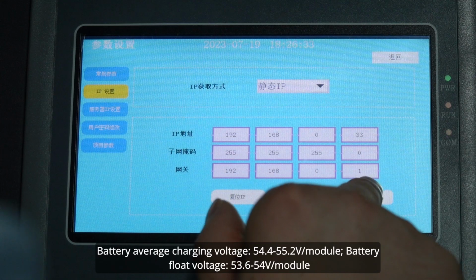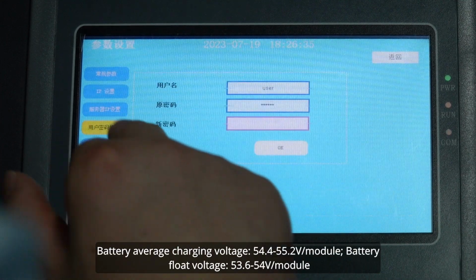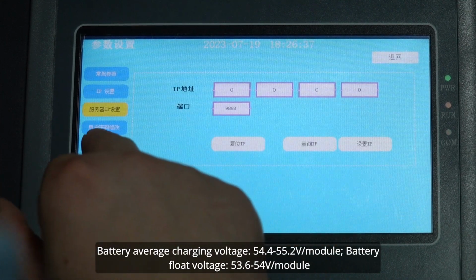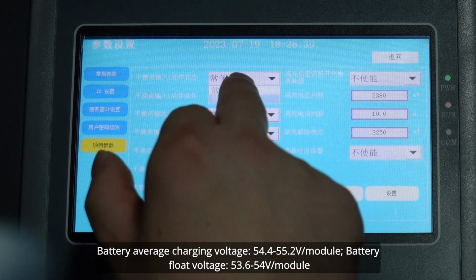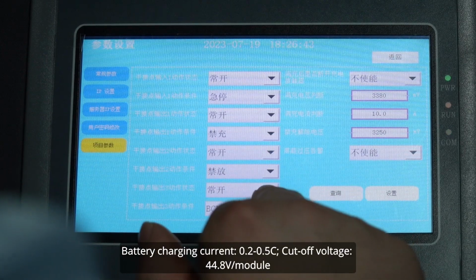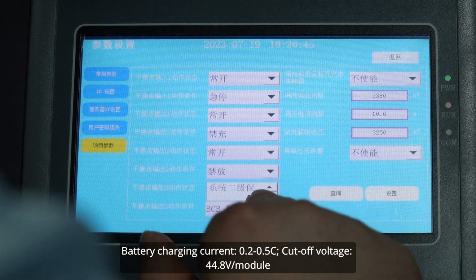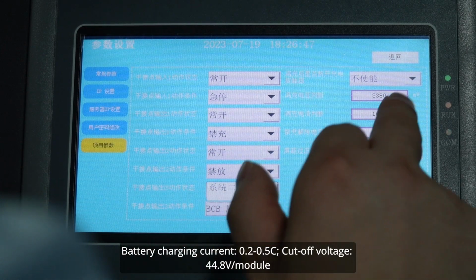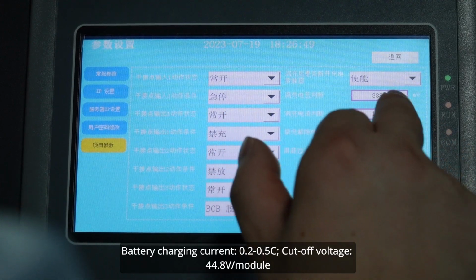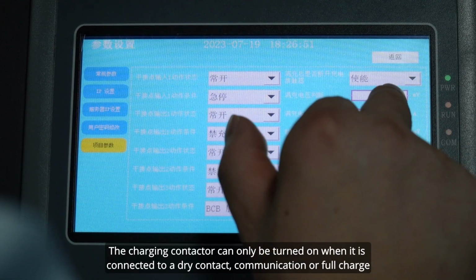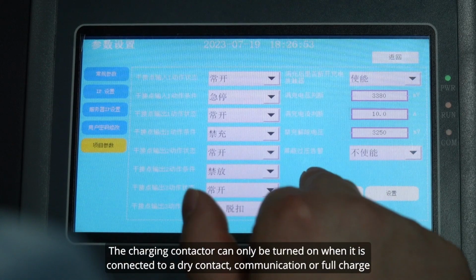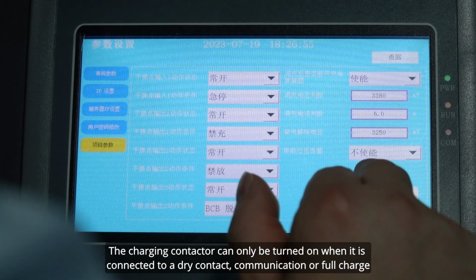Step 6. UPS parameter settings. Battery average charging voltage, 54.4-55.2V/module. Battery float voltage, 53.6-54V/module. Battery charging current, 0.2-0.5C. Cutoff voltage, 44.8V/module. The charging contactor can only be turned on when it is connected to a dry contact, communication, or full charge.